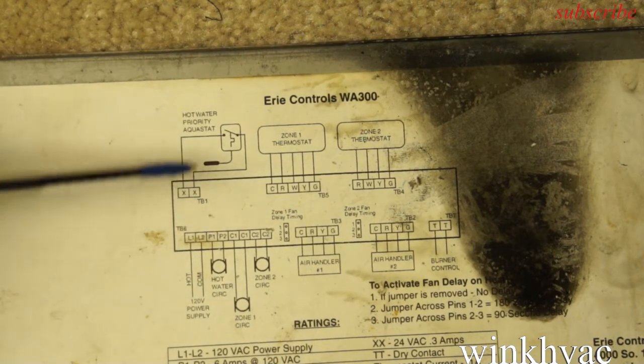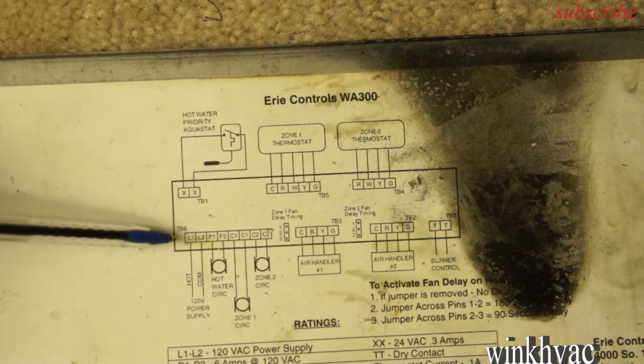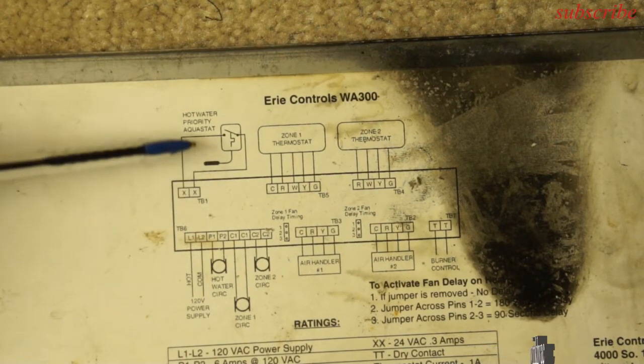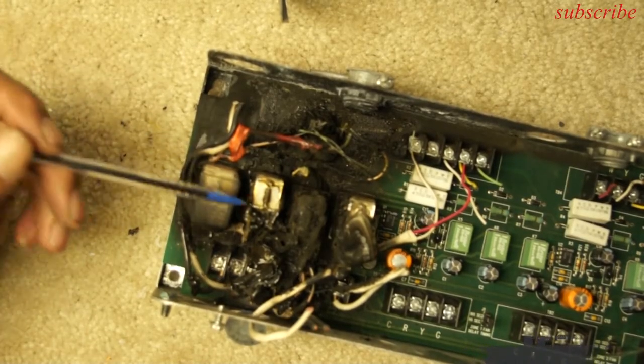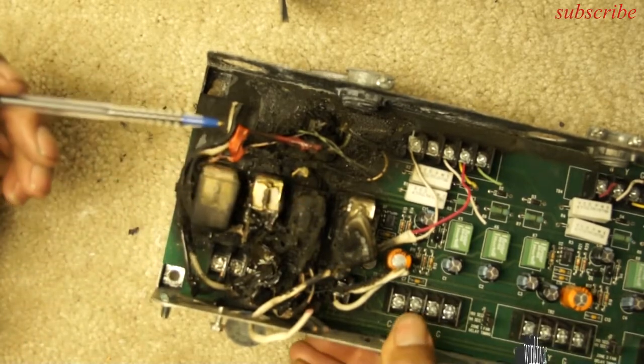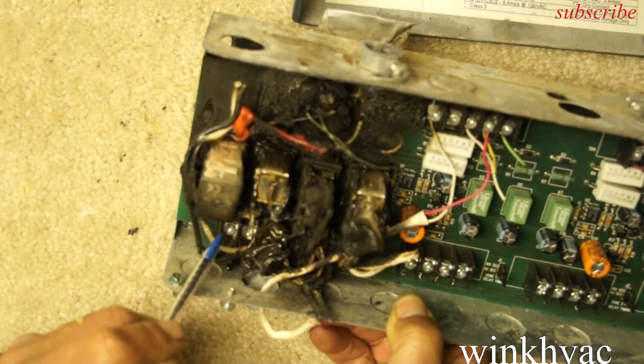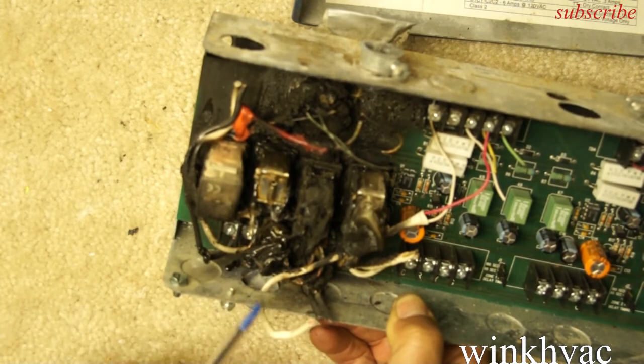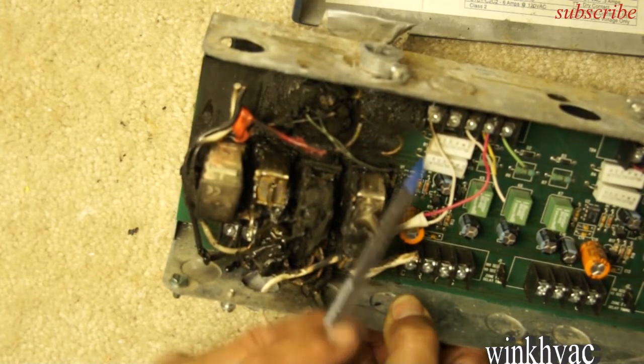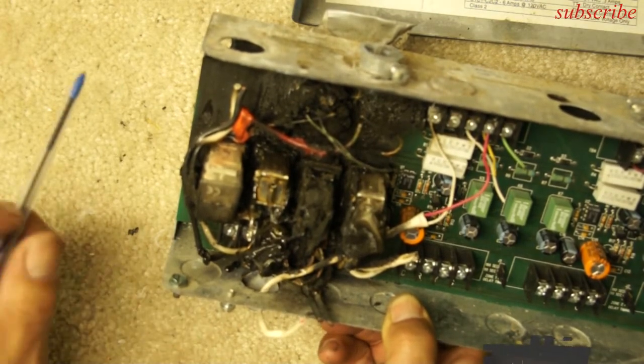Now, regardless, this shouldn't ever happen really. This control should have some kind of safety — even in the wire, 15 amp. Now let's look at the control itself. This is all the relay over here for the circulator — it's fitting over here. And the relay does its thing, it's energized — the circulator with thermostat one and thermostat two and any other circulator.